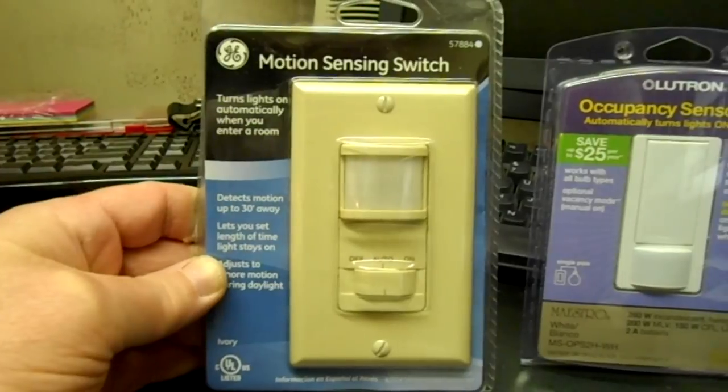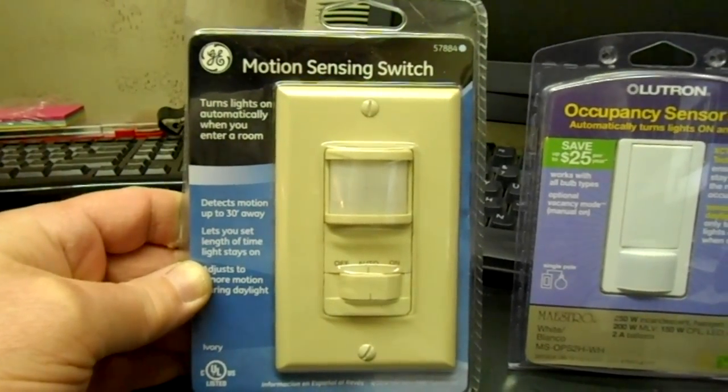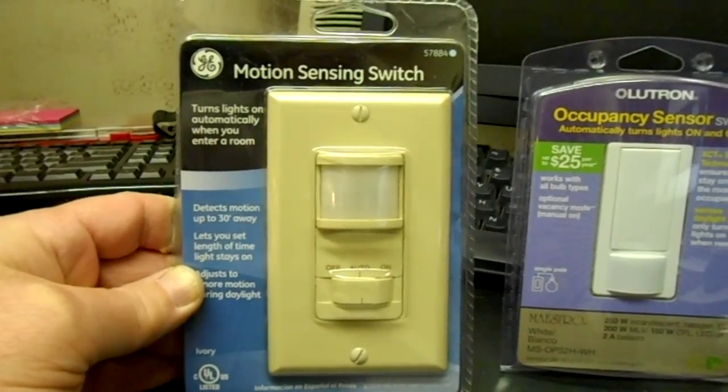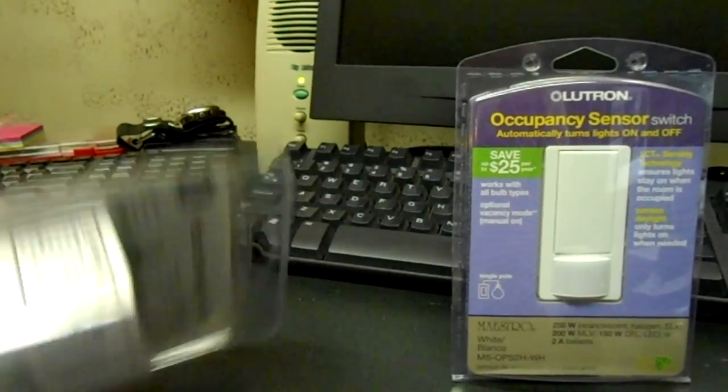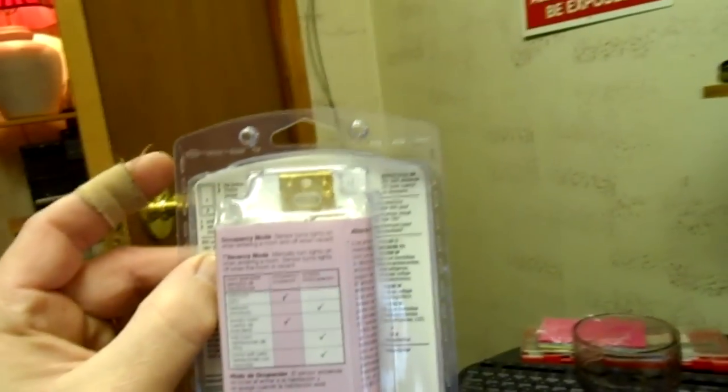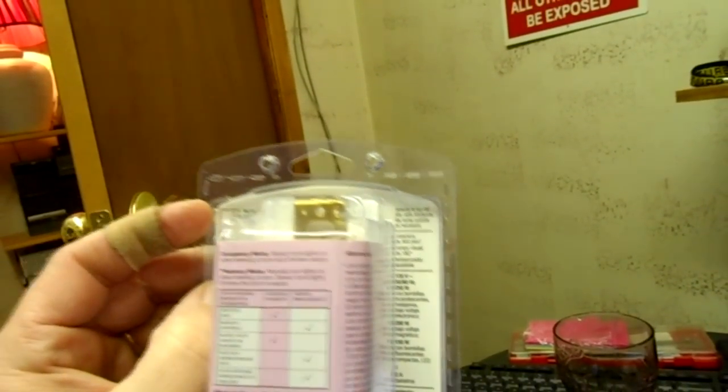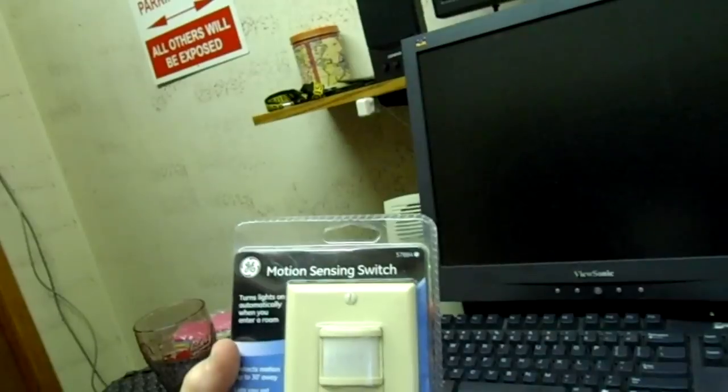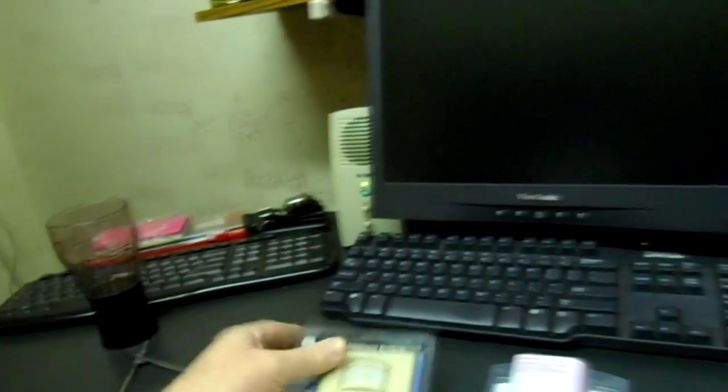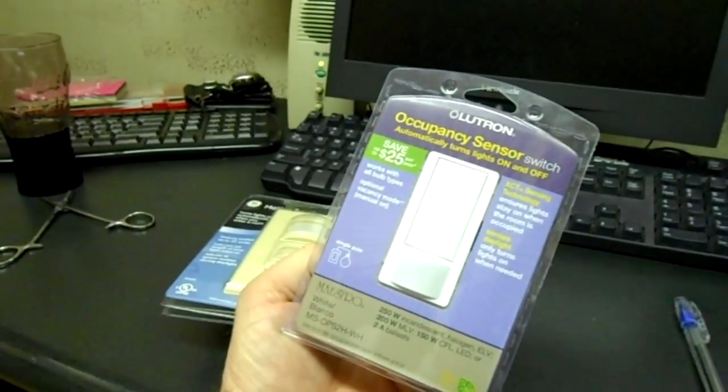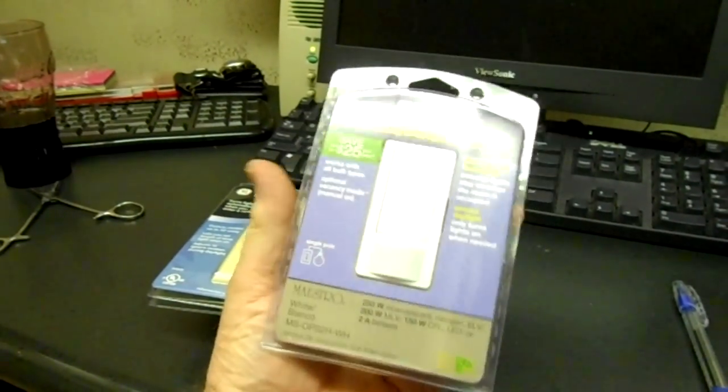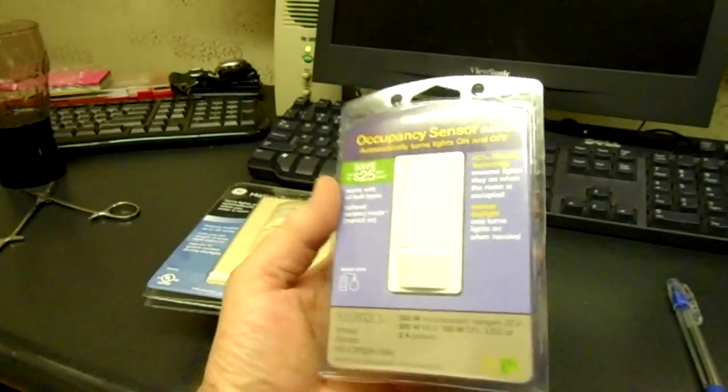They're rated for about the same capacity, like 250 watt incandescent bulb or 2 amp ballast. So the 30 foot range seems to be pretty normal on these things. This one says that it will cover up to 900 square feet of coverage and 180 degree view, and I think this is the same except it's only like 175 degree. This is the General Electric and this is the Lutron, so I'm gonna go ahead and hook these up.